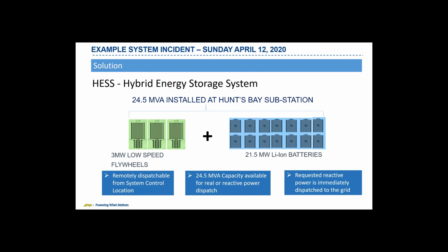They can just easily click into the SCADA system and tell the energy storage system how much real power or reactive power to dispatch. And like I said before, that entire 24.5 MVA capacity is available, so they can do real power, reactive power, or a mix of the two depending on the situation, and whatever they select will be available immediately to the grid.